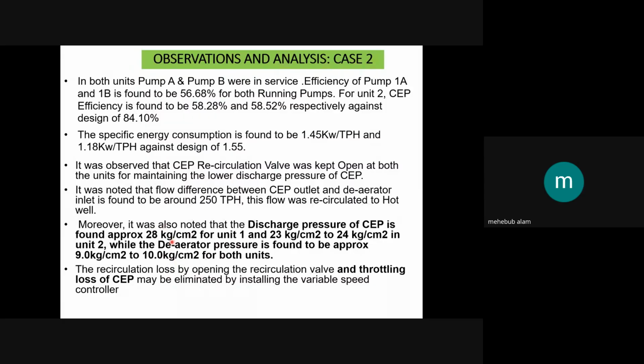So this huge discharge pressure is not actually required to meet the deaerator pressure, because we have to send the water from the CEP to the deaerator. So there is a huge gap actually. And through the recirculation valve, a loss occurred, which can be eliminated. This is a very high rating motor, so if we install a VFD, that will serve our purpose, and we can save a very good amount of power.